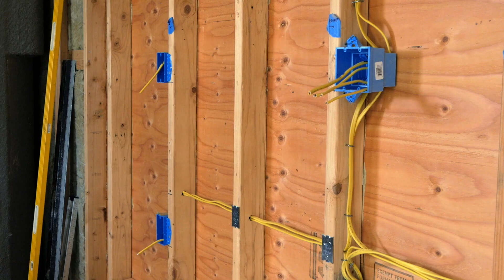And more to the point, even though there is not an inspecting legal body for tiny houses right now, that doesn't mean that we shouldn't be wiring things to code anyways. So just a quick word on language here, because this is a little bit confusing. If you're buying combination arc fault circuit breakers, it's important to understand that combination arc fault circuit breaker doesn't mean that it's a combined GFCI AFCI. Combination in this case just means it can detect series or parallel arcs. If you're looking for a combined AFCI GFCI, what you need to get is a dual purpose AFCI GFCI circuit breaker.